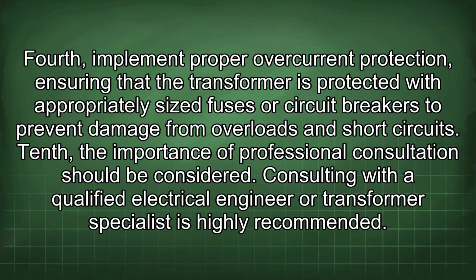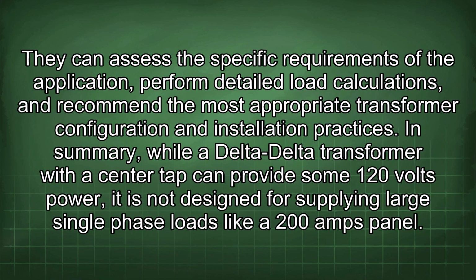Tenth, the importance of professional consultation should be considered. Consulting with a qualified electrical engineer or transformer specialist is highly recommended. They can assess the specific requirements of the application, perform detailed load calculations, and recommend the most appropriate transformer configuration and installation practices. In summary, while a delta-delta transformer with a center tap can provide some 120 volts power, it is not designed for supplying large single-phase loads like a 200 amps panel.